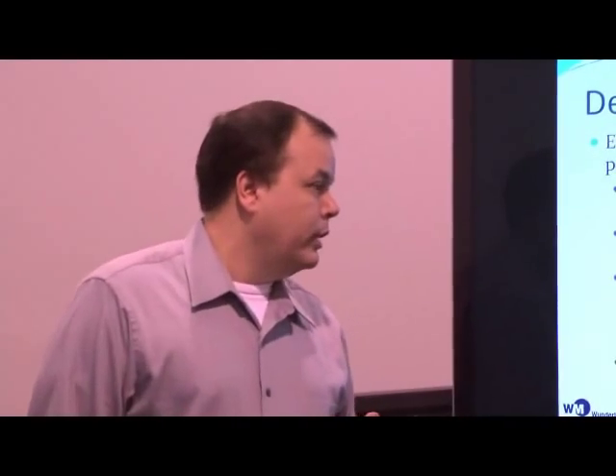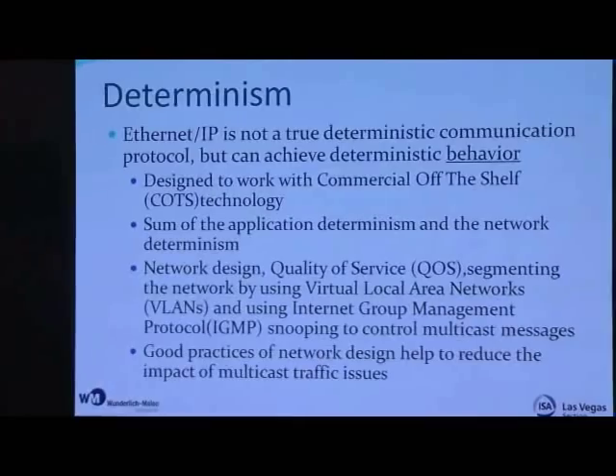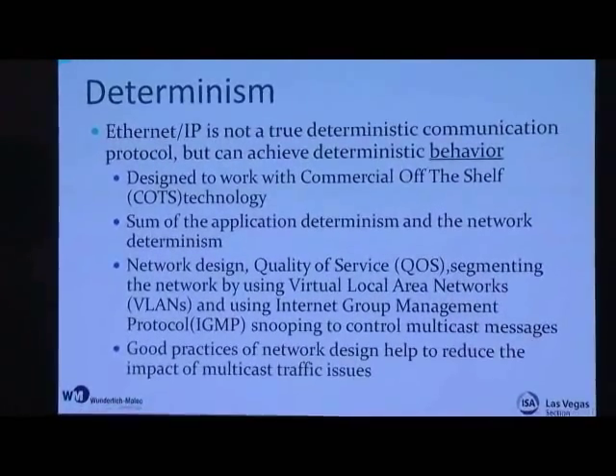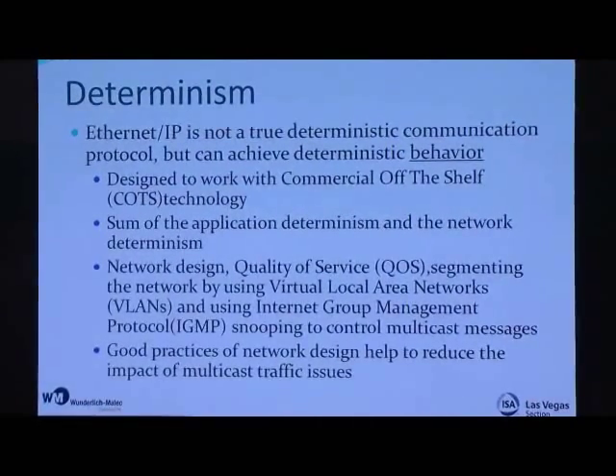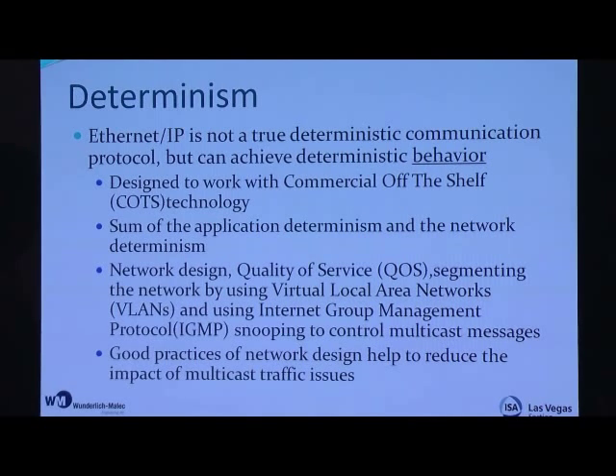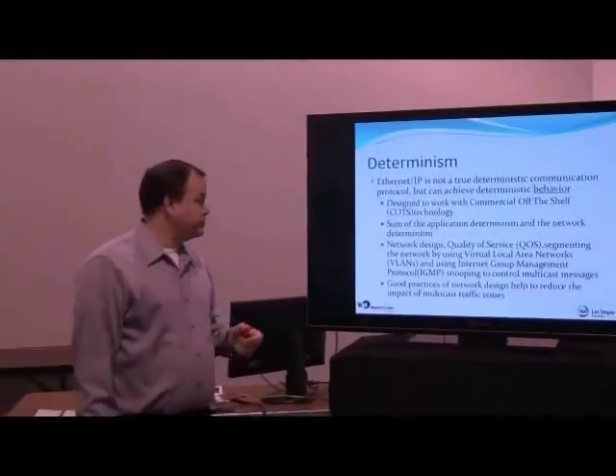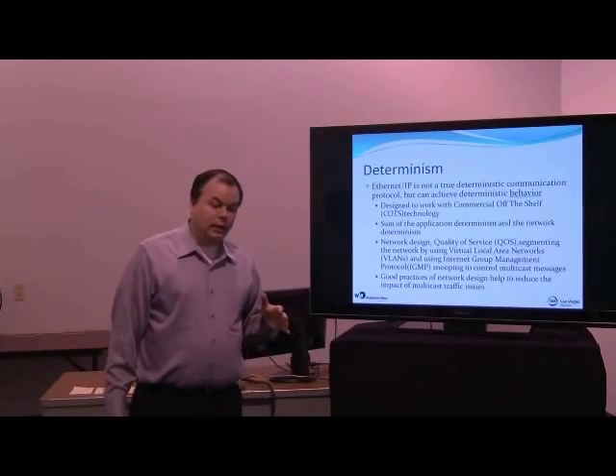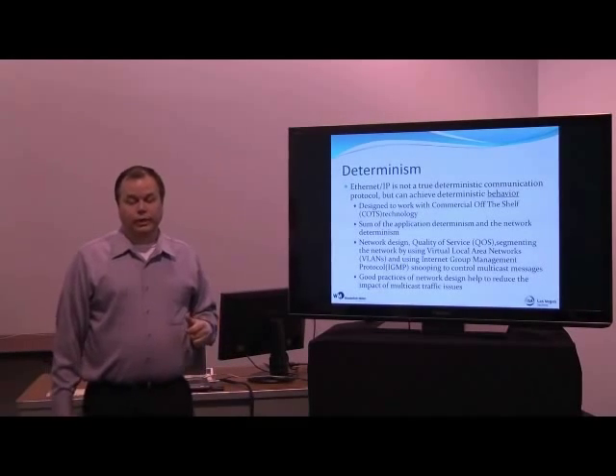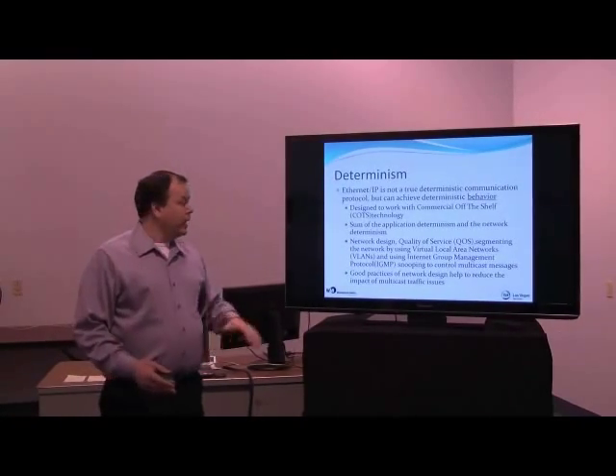One issue that has always surrounded industrial Ethernet protocols is determinism. Ethernet IP is not a deterministic network — meaning we cannot guarantee how long it takes for a message to travel and for the response to come back. If a switch goes down and the router has to reroute traffic, that adds latency that is not controlled or easily predicted. The reason Ethernet IP is non-deterministic is that it is designed to work with commercial off-the-shelf technology — most anyone's routers and switches will work with Ethernet IP, which provides advantages but also some disadvantages.